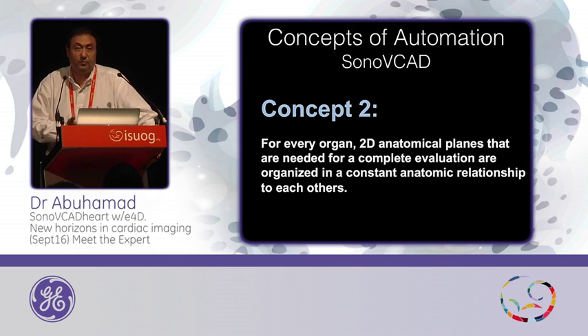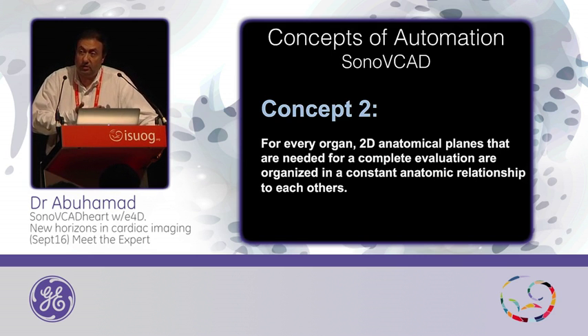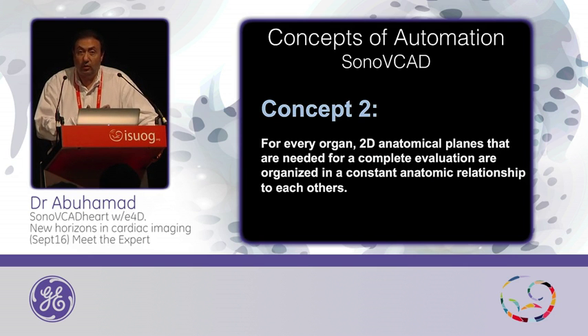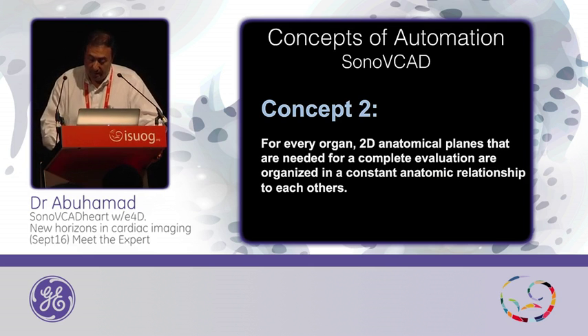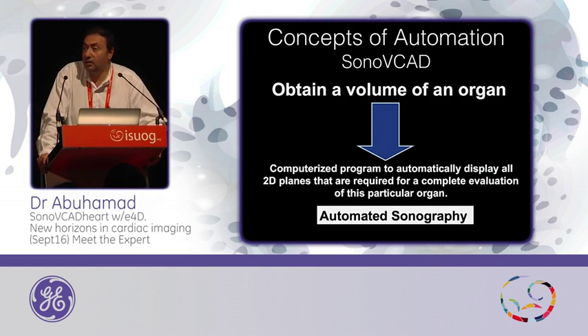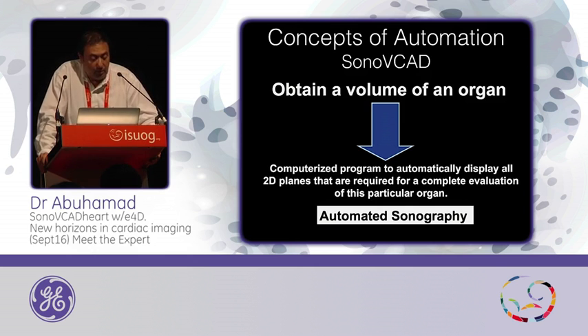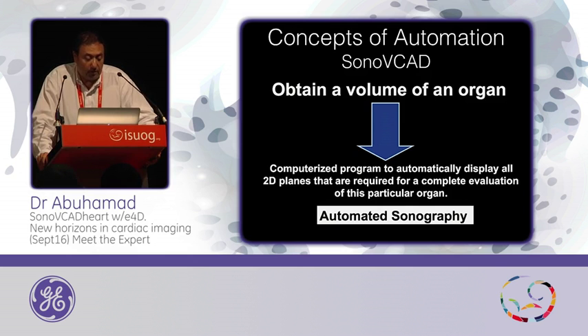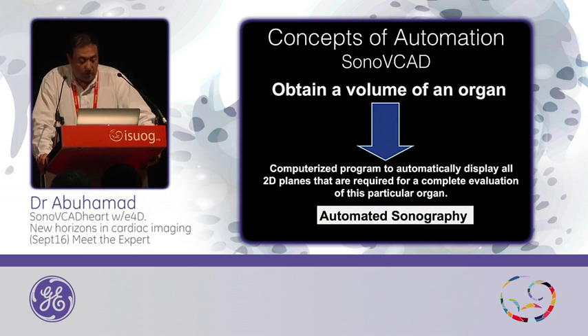We know that to go from the four-chamber view to the pulmonary artery, we tend to slide up in the chest without any rotations, and to get the LVOT plane, we have to do some rotation with a slight slide up. So the concept came to reality that you can obtain a volume of an organ such as the fetal chest and create a program that will automatically display all the 2D planes required for a complete evaluation of that organ — and hence, the beginning of automation in the evaluation of the fetal heart.